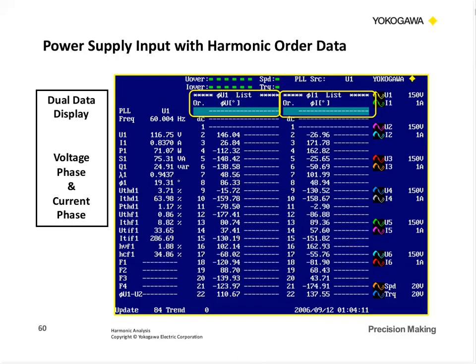We can look at the phase of each one of these harmonic components. And this could be helpful if we're trying to put in some filters to clean things up. You'll know the amplitude, you'll know the frequency, you'll know the phase between the voltage and the current. So if you're doing your filter design, hopefully this information will give you what you need to design maybe an RLC filter to block some of these harmonics.